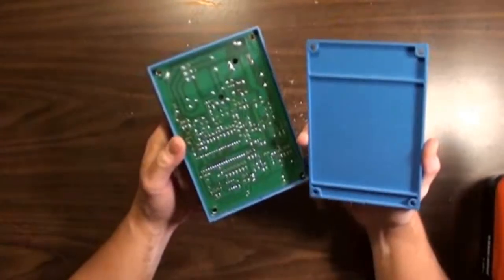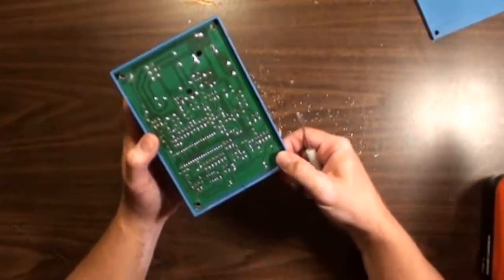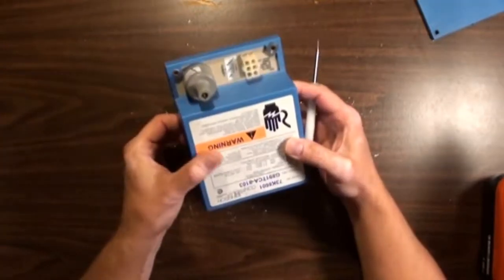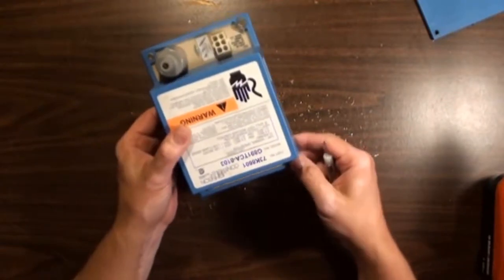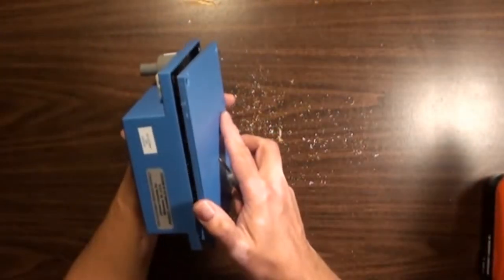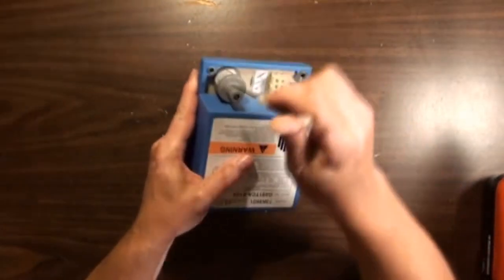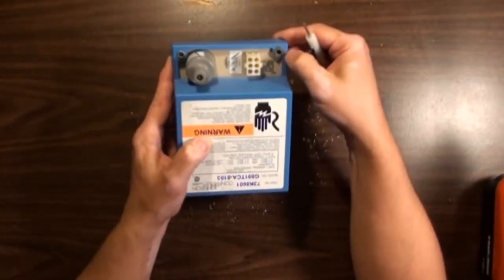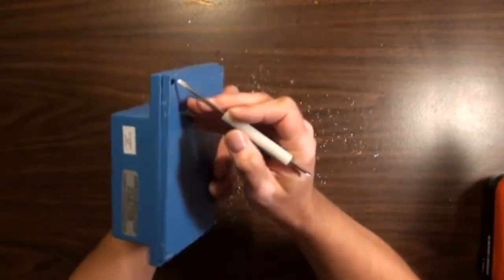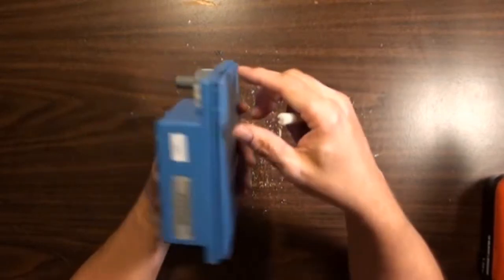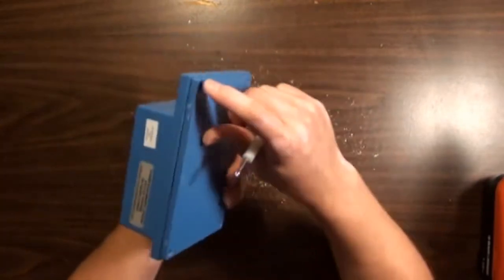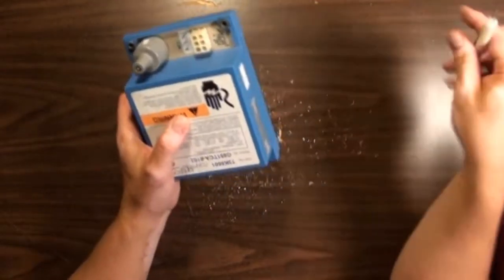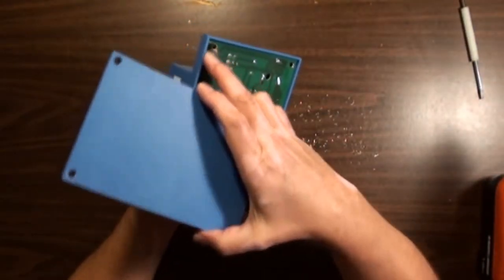There we go. There's the circuit board, there's the cover. When we get done, this is going back on here. I don't remember if we reuse these just the way they are, because this bolts into the system and screws go right here. We might be leaving those on there and then putting this back in. When we put our screws through there it'll hold this in place, because we don't want to tighten the screws and then break the corners of this plastic. We definitely got to have our ground on this one, so the ground hits here and it's also supposed to hit the metal on the furnace itself.